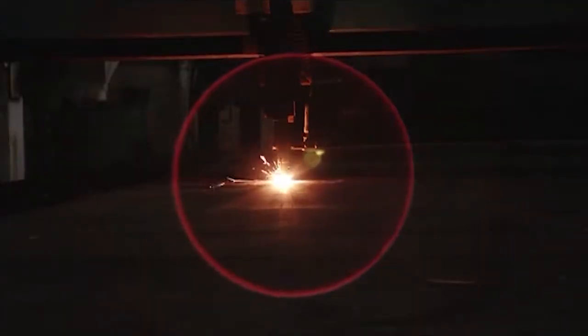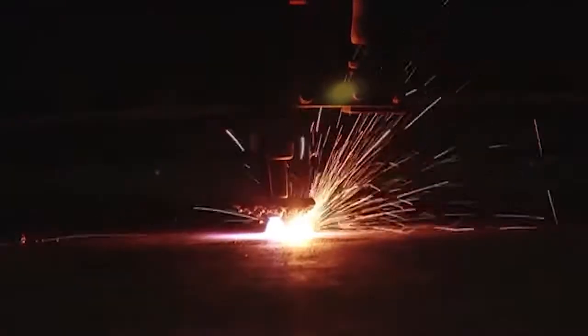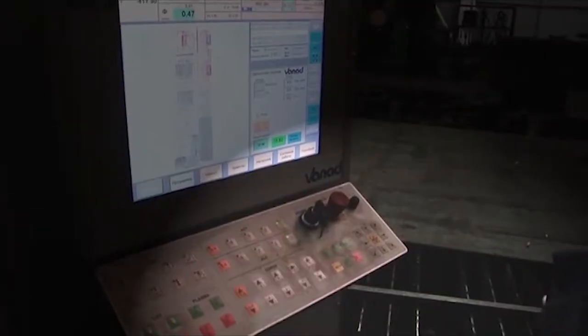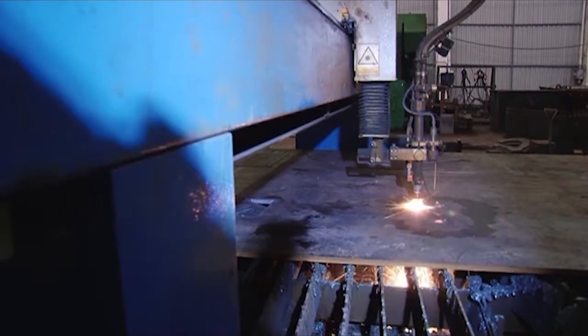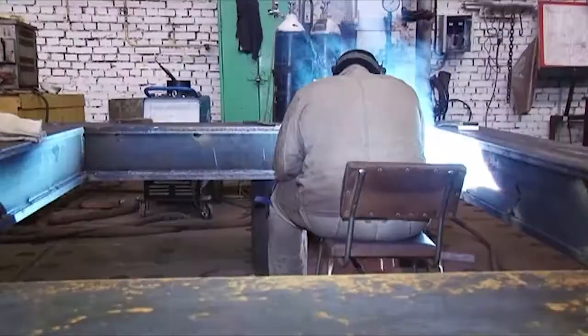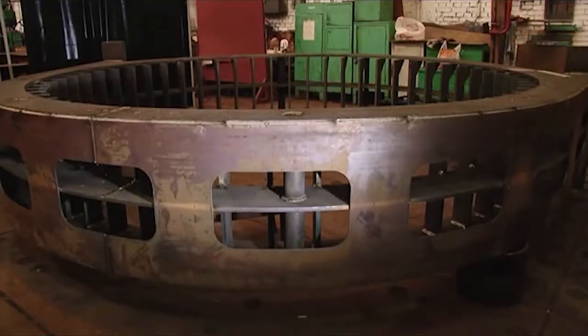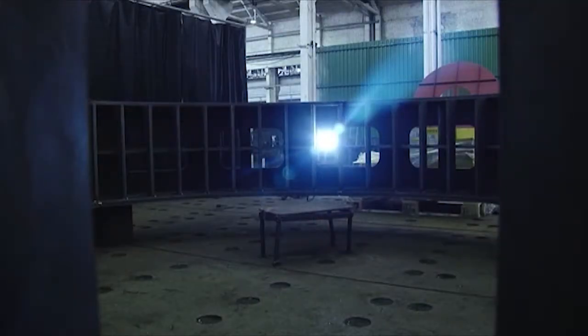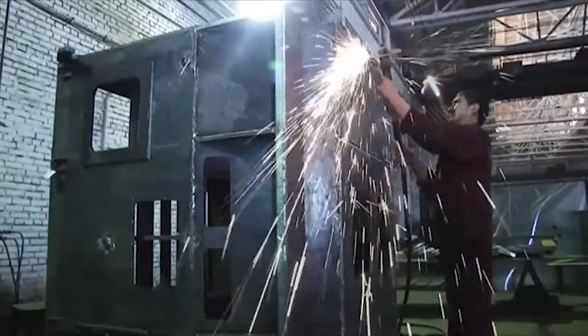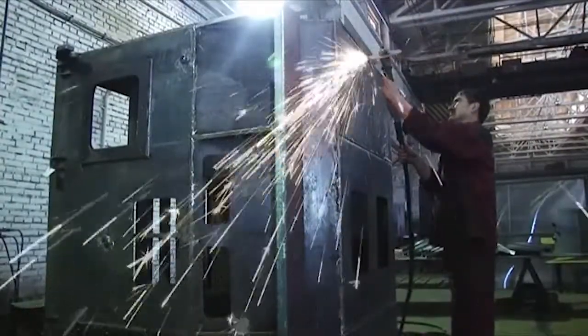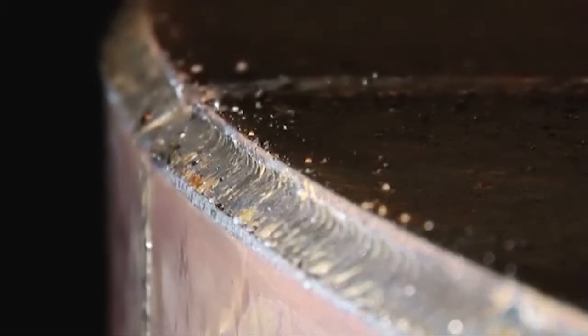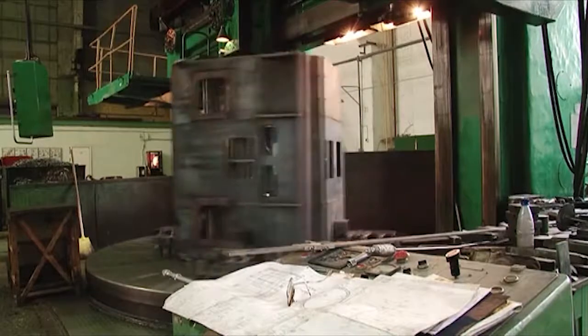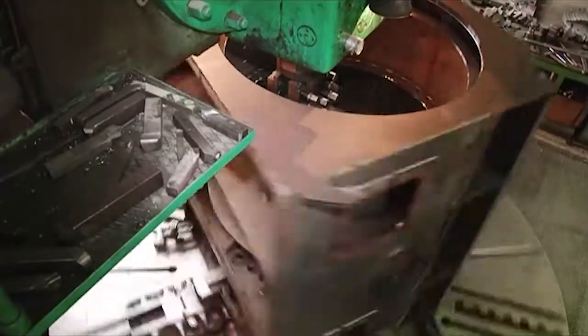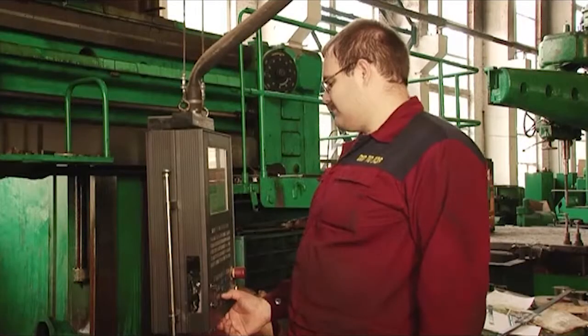One of the first operations is sheet materials nesting layout by means of gas cutting. This operation is carried out with NC machine tools guided by a controlling program. The sheets are then welded into an integrated body. Then, welded seams are pneumatically dressed after the assembly of the main stator body. The frame mounting faces are machined by a rotary table milling machine for stator iron stacking. The milling machine is equipped with NC rack to provide the required accuracy of internal surface machining.